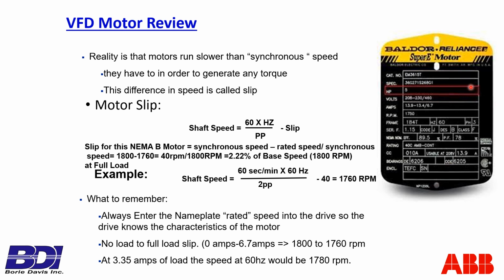So if this motor fails, you could go find another motor. I'd assure you, unless you bought the exact same motor, you could go buy a different motor manufacturer. Not that I want you to, but you get a 5-horse motor rated 460 volts and 7 amps, you'd say base speed 1800, and you bring that motor in, it might be rated 7 amps and 1755 RPM, and you'd be okay with that, and so would the load. Okay, so the nameplate is just for purposes really of one point of operation. With the drive you get infinite points of operation.